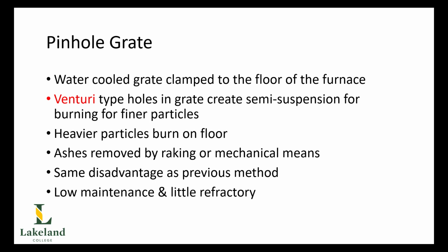Now, with regards to these Venturi type holes, they end up creating what's known as a semi-suspension to burn these finer particles, which in other words means we get a better intimate mixing of our air and the fuel on the bottom of the furnace floor, so we get a more complete and even burn. It also turns the fuel particles over, so the light particles move to the top and the heavier particles move to the bottom so that they can combust.